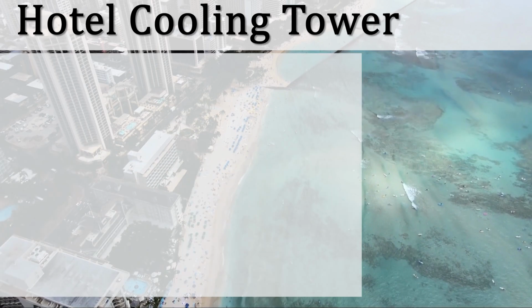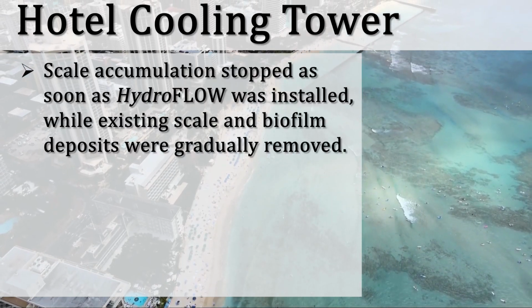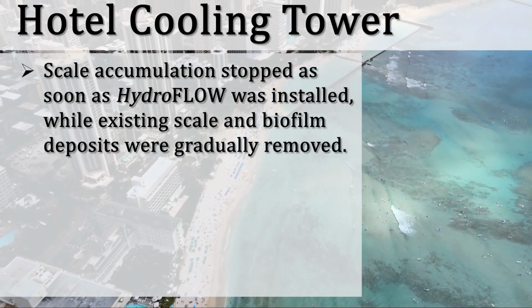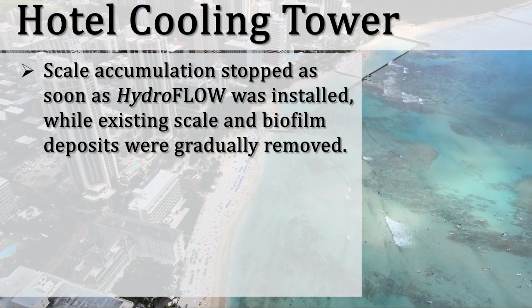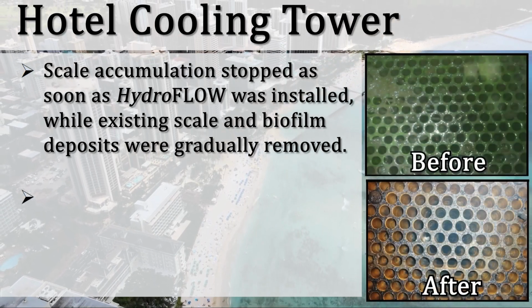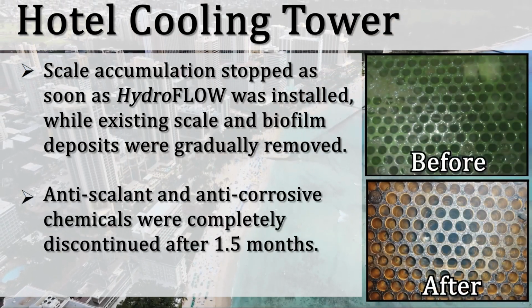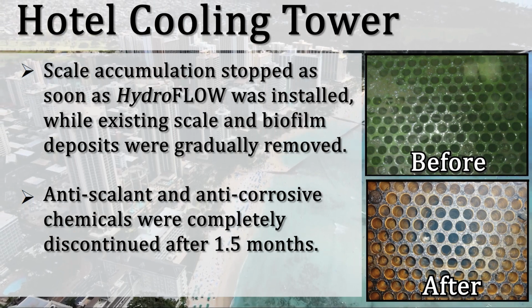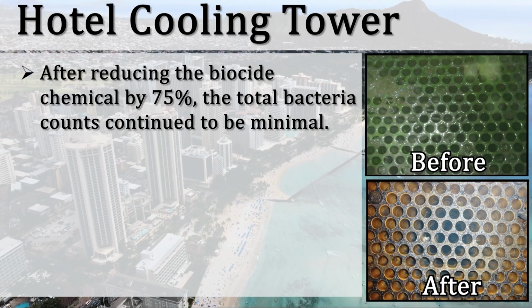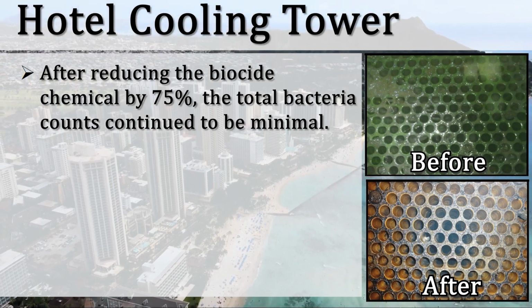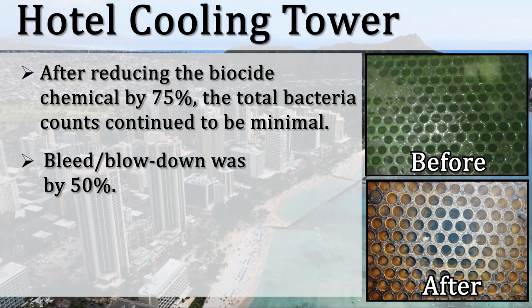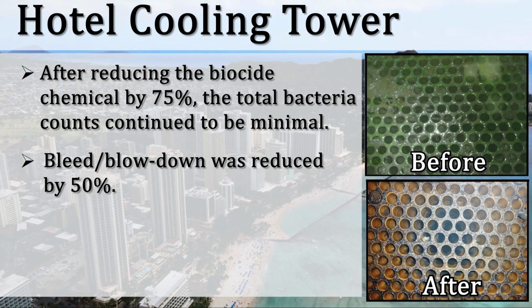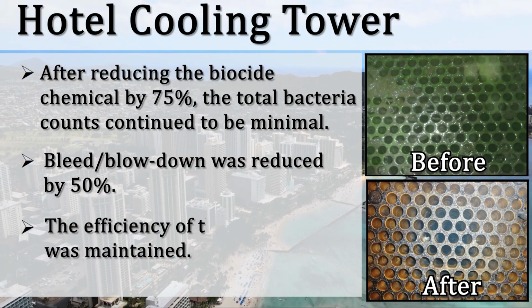Results: scale accumulation stopped as soon as HydroFLOW was installed, while existing scale and biofilm deposits were gradually removed. Anti-scalant and anti-corrosive chemicals were completely discontinued after 1.5 months. After reducing the biocide chemical by 75%, the total bacteria counts continued to be minimal. Bleed blowdown was reduced by 50%. The efficiency of chillers was maintained.